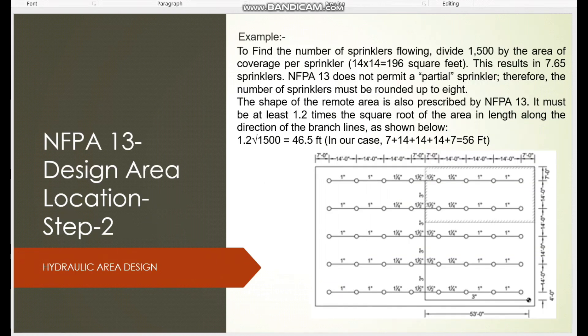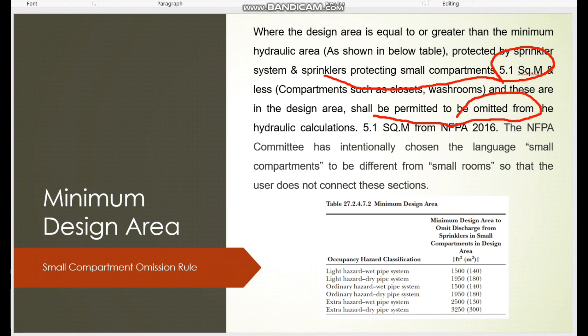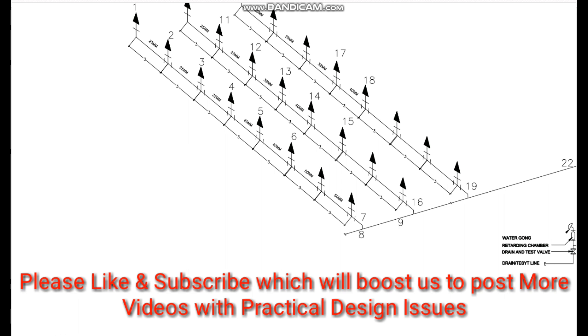One more very interesting concept: suppose your hydraulic area contains a toilet room. The question is whether to include it in the calculation. Per NFPA 13, sprinklers protecting small compartments less than 5.1 square meters shall be permitted to be omitted from the hydraulic calculation. So if the toilet in your hydraulic area is less than 5.1 square meters, you can omit it and use the balance area, but you must still comply with the 1500 square feet minimum requirement.